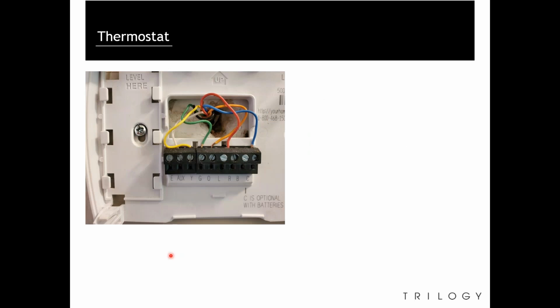So while we talk about the thermostat, let's make sure that that thermostat is wired properly. Our white is going to be our heat. Our yellow is our air conditioner. Green is for the fan. Red is a constant 24. Blue is our common. Orange is for reversing valve and cooling mode on a heat pump application.